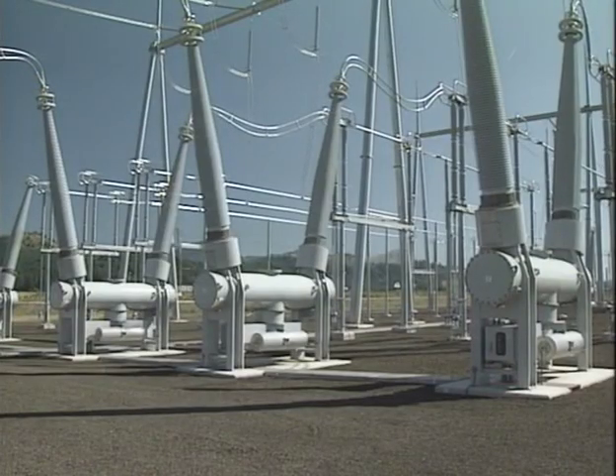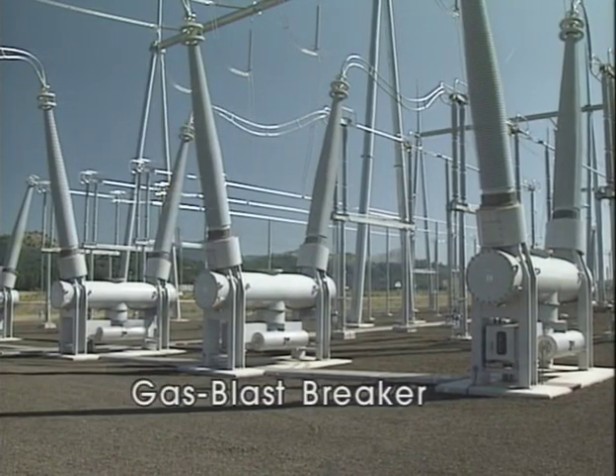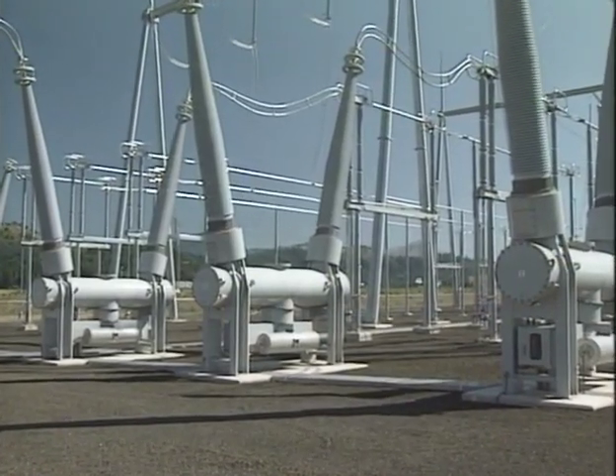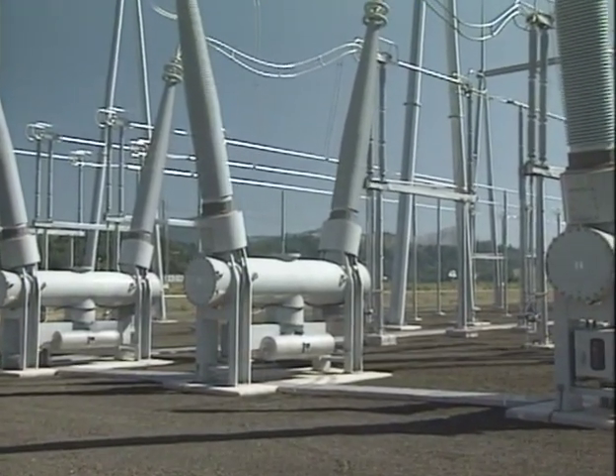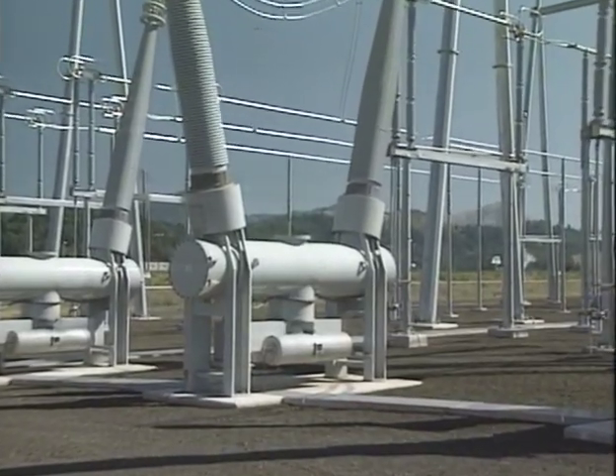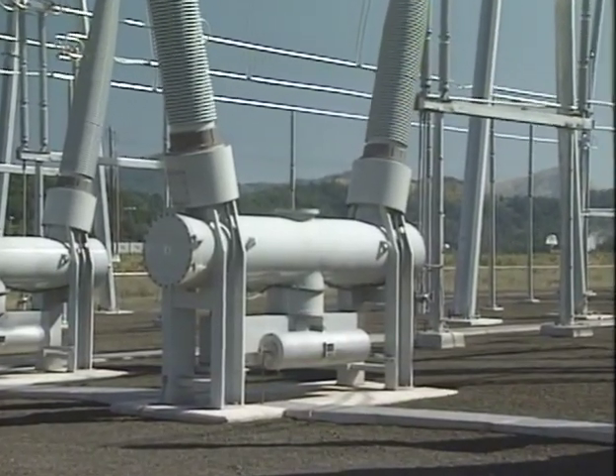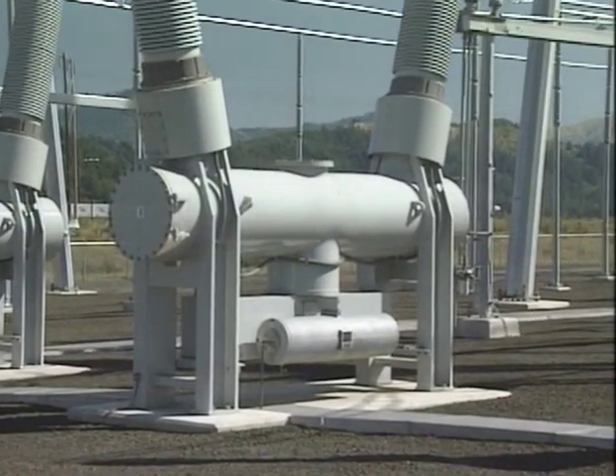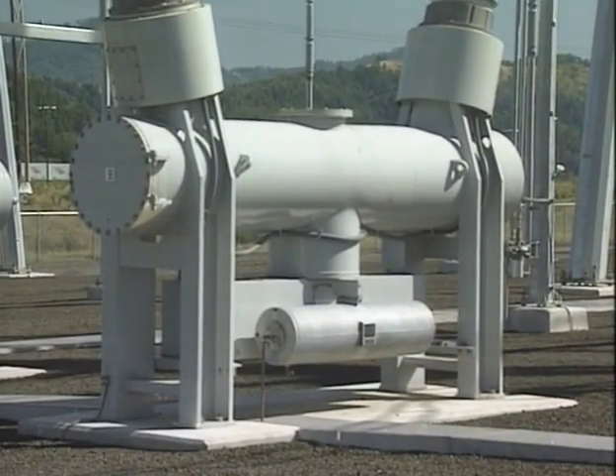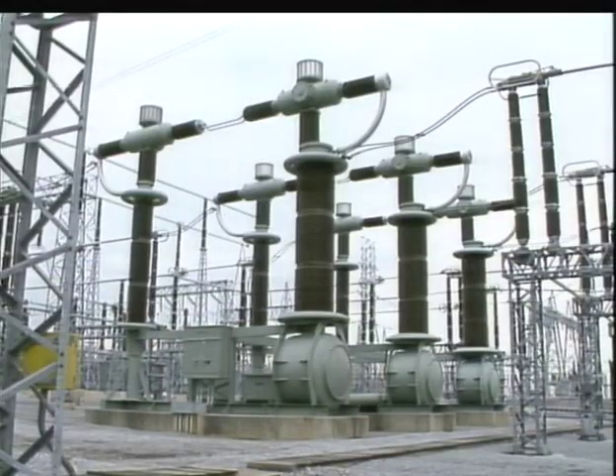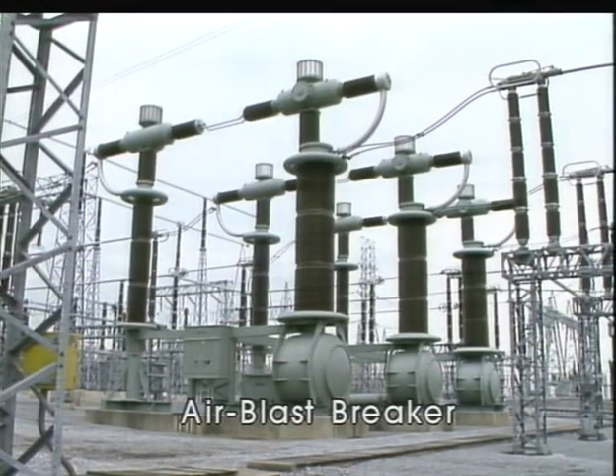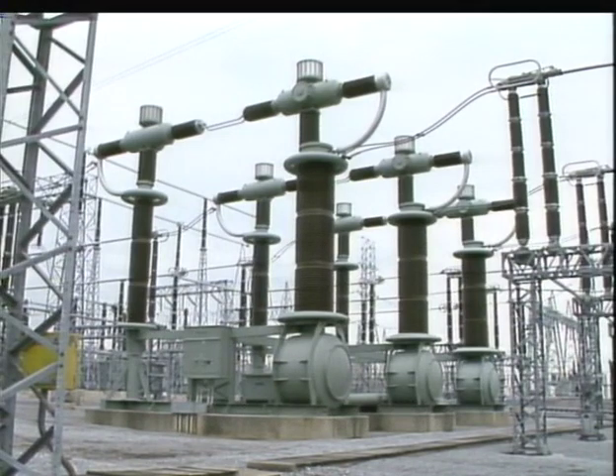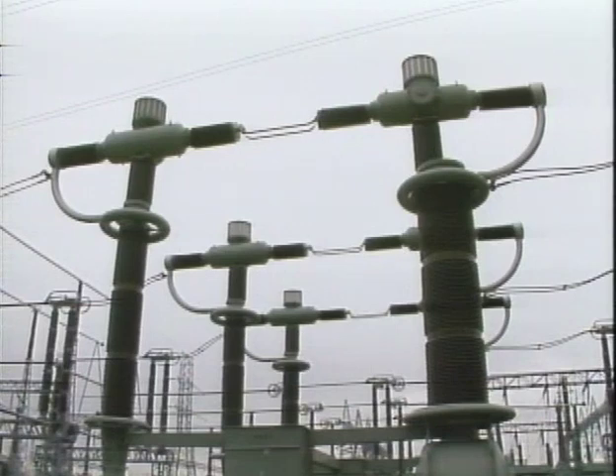A fifth type of power circuit breaker is the gas blast breaker. Its contacts are also surrounded with low-pressure SF6 gas, but it also maintains a separate reservoir of gas under high pressure. When the breaker contacts open, the high-pressure gas is released through the arc in a sudden blast to stretch, cool, and extinguish it. A sixth type of power circuit breaker is the air blast breaker. In this type of breaker, the contacts are surrounded by compressed air. When the contacts open, the compressed air is released in a forceful blast through the arc to the atmosphere, extinguishing the arc in the process.